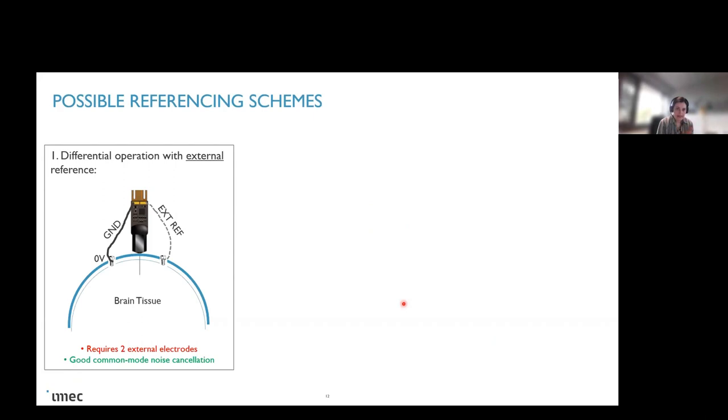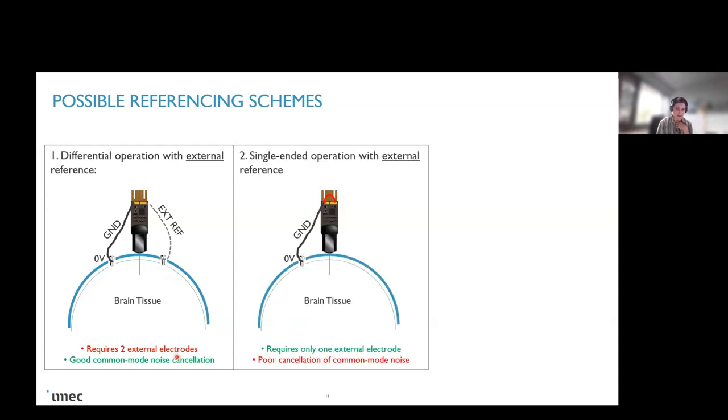So I will explain here in three different reference schemes. The first one is to have your external reference. As explained before, this is a differential operation where the external reference is connected as well. For example, through a screw or other means, there are many techniques to connect your external reference. The problems here, if you want to have this differential operation, means that your ground is separate from the reference, you will need two external electrodes. And this, for certain experimental setups, can be an issue. But you will have good cancellation of your common noise.